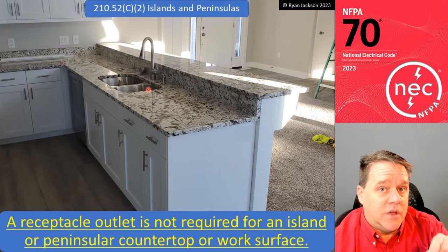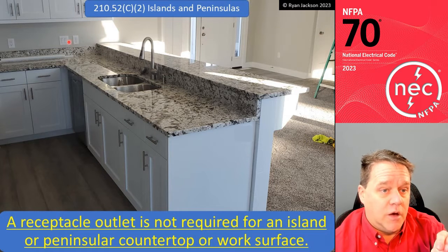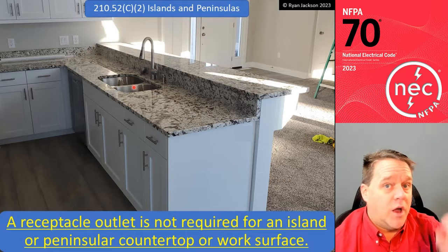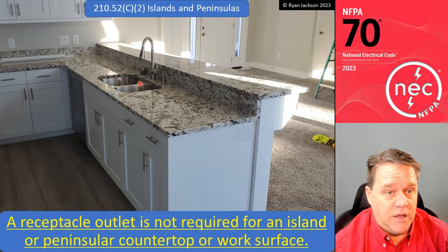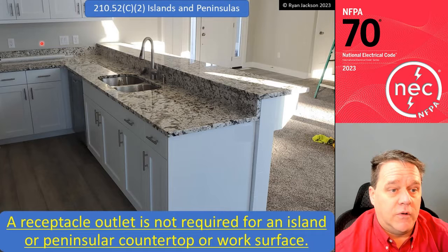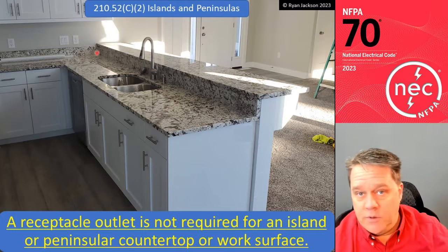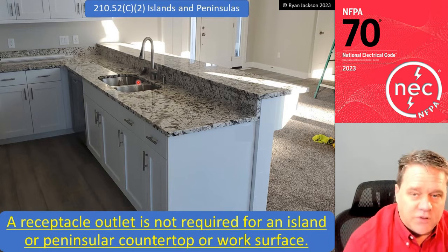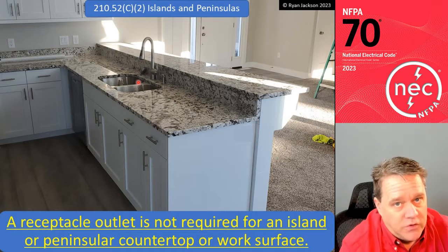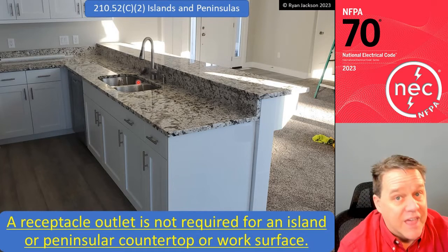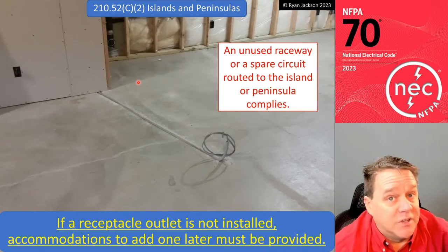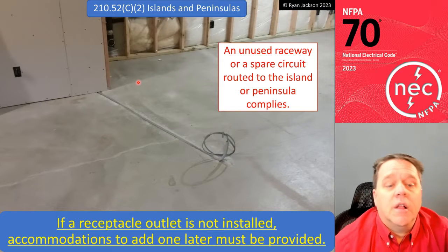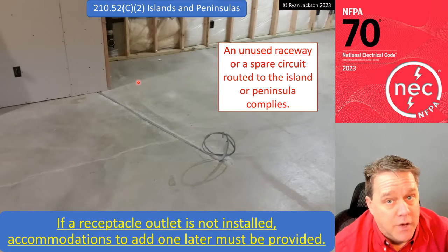So how many receptacle outlets are on this peninsula right now? 1. How many are required? 0. You don't need any. All right, so you could move that receptacle over and that would still be fine because you don't need to have any. No receptacles required for islands, no receptacles required for peninsulas. However, if a receptacle outlet is not installed, then accommodations to add one later must be provided.